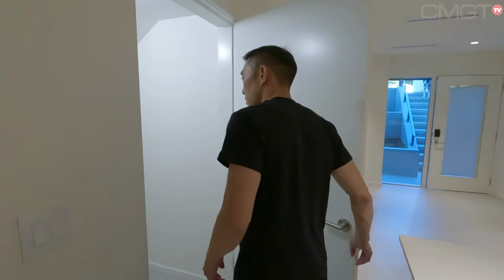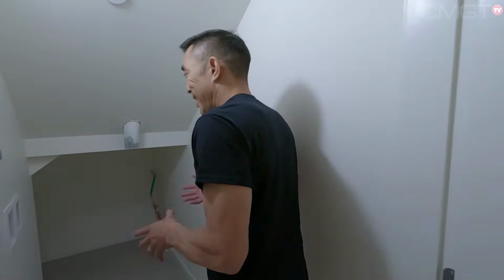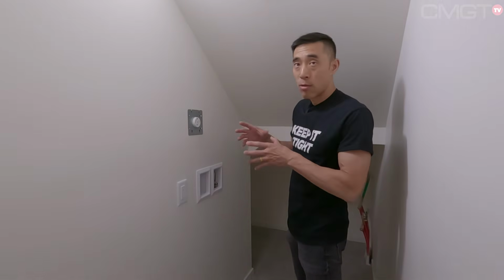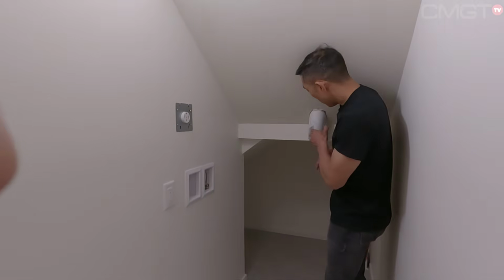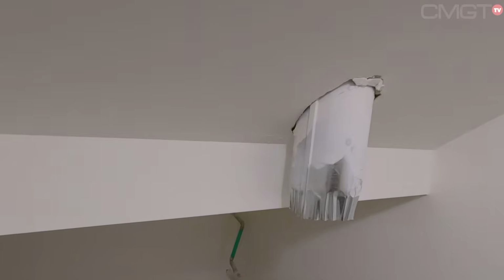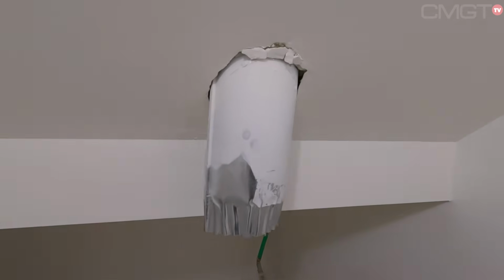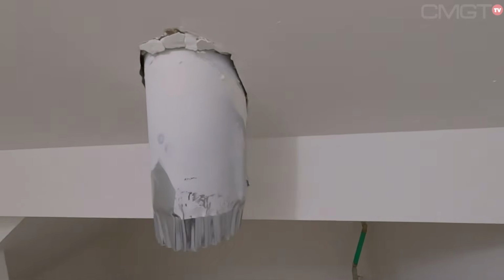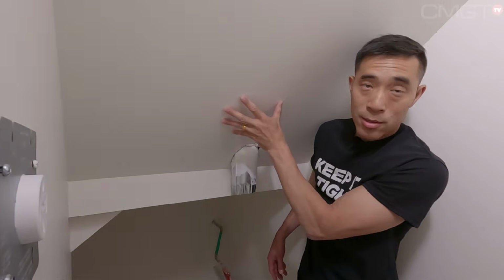On the topic of life and safety and secondary suites, because this area is separate from upstairs, you want to make sure any penetrations coming through the fire-rated walls and assemblies are also fire-rated. In this case, we have yet to put the fire caulking around this penetration because this assembly is what separates upstairs and downstairs.